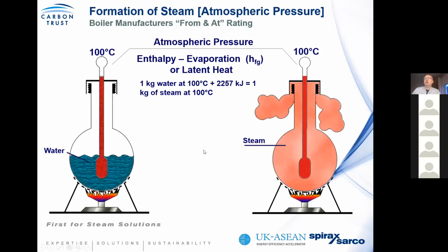Then to create steam, we need to add additional latent energy to a point where we get it up to high quality dry steam. At atmospheric conditions, we need to add an additional 2,257 kilojoules to produce 1 kg of steam at 100 degrees. The difference in the latent phase is that you change the phase or state of the water without a change in temperature. And this is important because it's a constant temperature energy addition process.